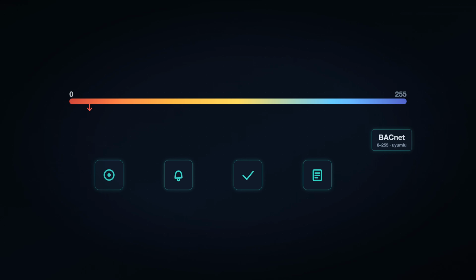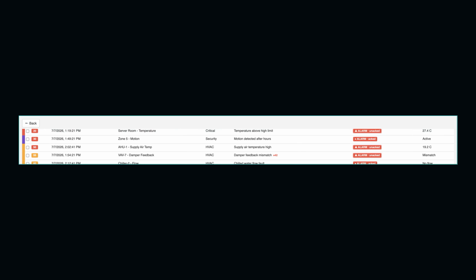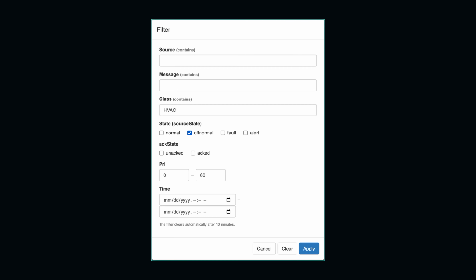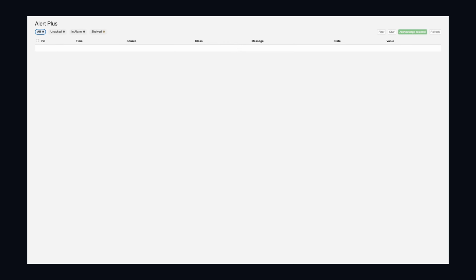Each alarm carries a priority in the 0 to 255 range. A lower value is more urgent, in keeping with the BACnet convention, and takes its color, its sound, and its acknowledgement and note rules from an alarm class. An alarm that repeats at short intervals is collapsed into a single line with a counter. The operator can shelve it temporarily, suppress it during maintenance, and filter by class, priority, or time. So even in a heavy alarm flow, the most critical alarm stays at the top of the list.